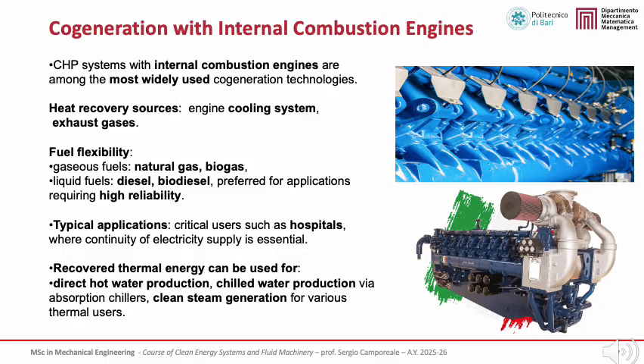We now introduce cogeneration with internal combustion engines, one of the most widely used CHP technologies. ICE-based CHP systems are particularly attractive due to their high electrical efficiency, operational flexibility, and wide availability across different power ranges. The main heat recovery sources are the engine cooling system and the exhaust gases, which together allow the recovery of a significant fraction of the fuel energy as useful heat.